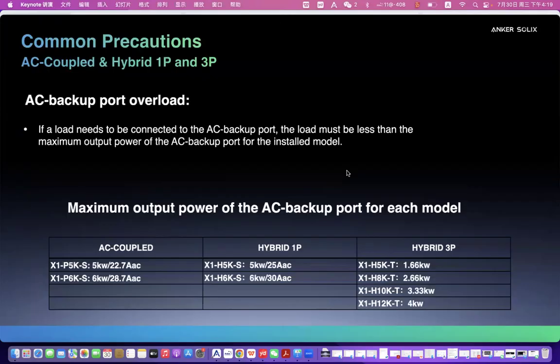And this part I need to emphasize again. For our hybrid single phase, we provide a 5 kilowatt and 6 kilowatt solution, and AC couple also provides 5 kilowatt and 6 kilowatt solutions. It will be easy. We recommend the backup loads do not exceed the rated power of this machine. For example, for 5 kilowatt, just connect 5 kilowatt. It will not be overloaded.